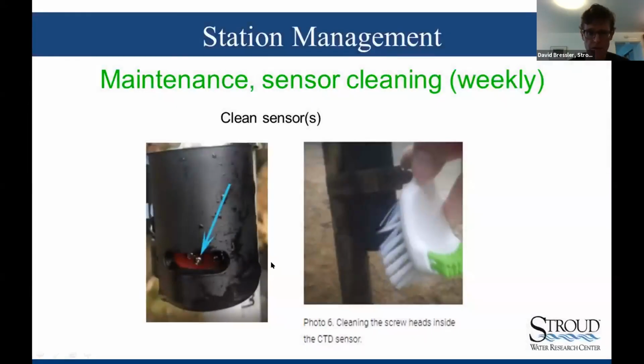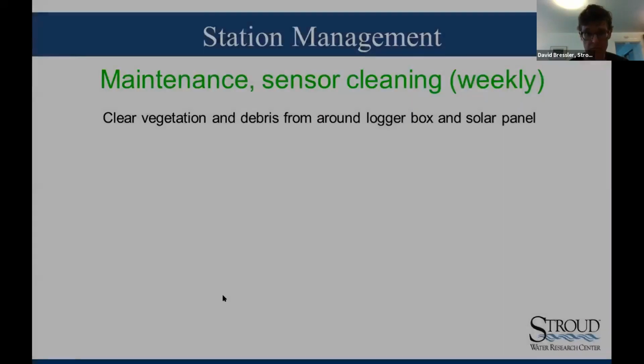One other thing to mention here, George is going to talk about this as well, but you can get bigger particles that get wedged in there and then affect the pressure transducer. So at those times, it can be important to take the whole bundle out of the stream and look, and George will get into some of those types of details.